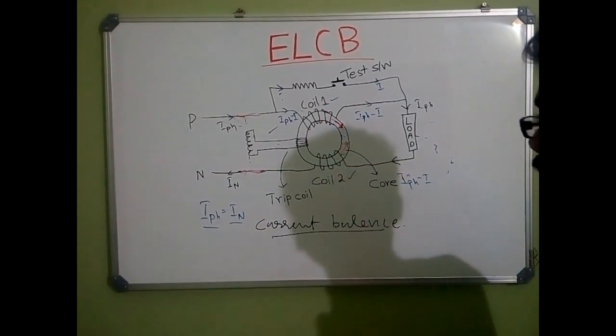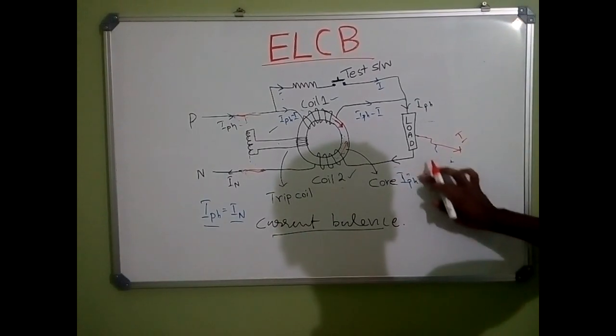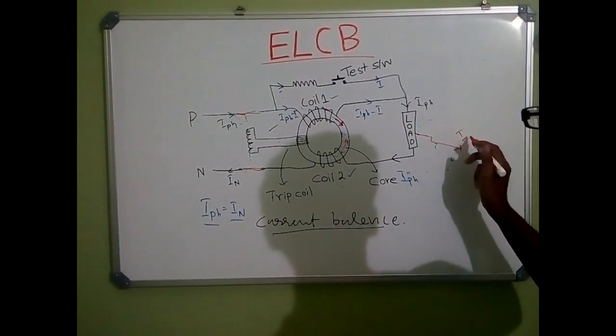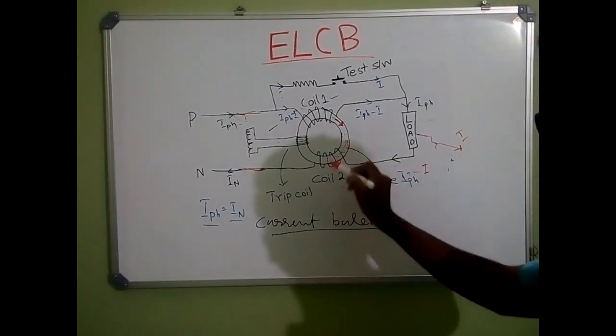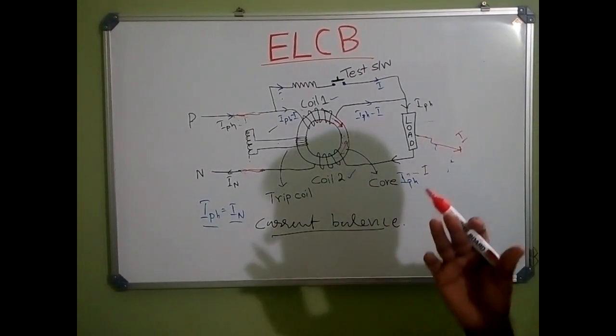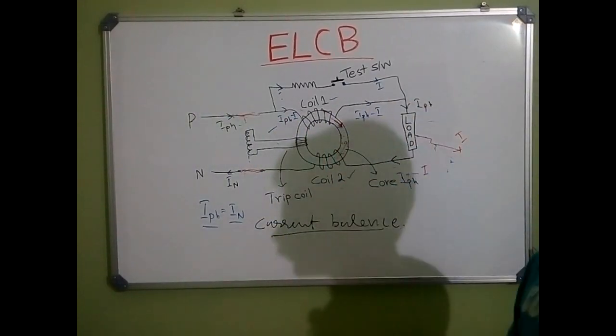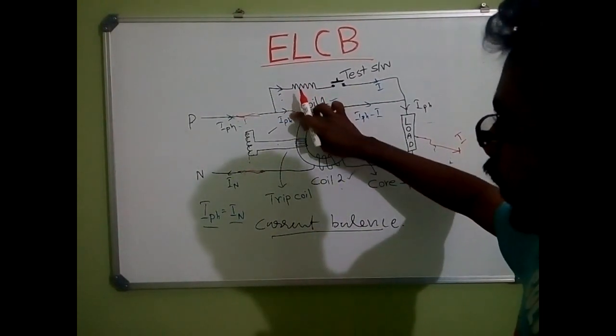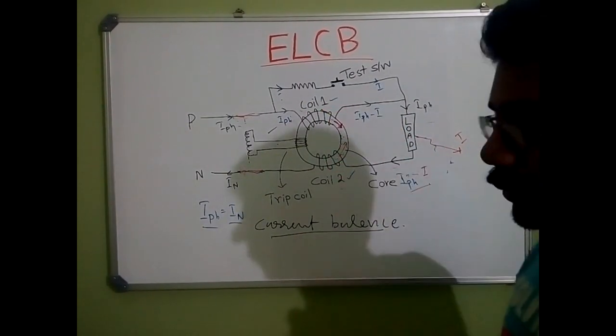Now we are going to look at what happens when a leakage current occurs. Let us say a leakage current of I occurs here due to insulation failure. I-phase is the entering current to the load. So the net current coming into Coil 2 is nothing but I-phase minus I. This current passes through Coil 2 and reaches neutral. Current through Coil 1 is I-phase, and current through Coil 2 is I-phase minus I, so the currents in Coil 1 and Coil 2 are not the same.